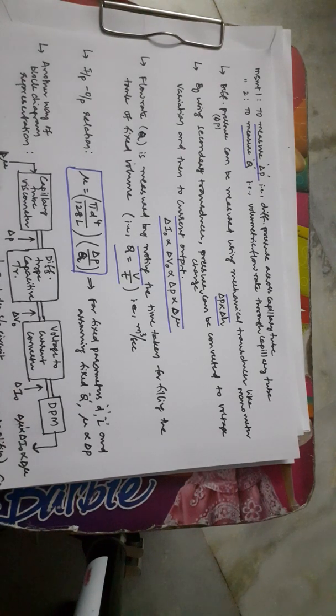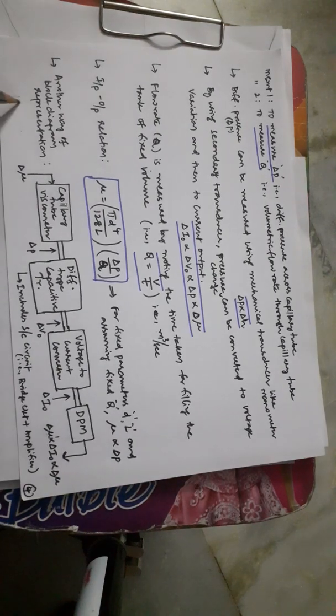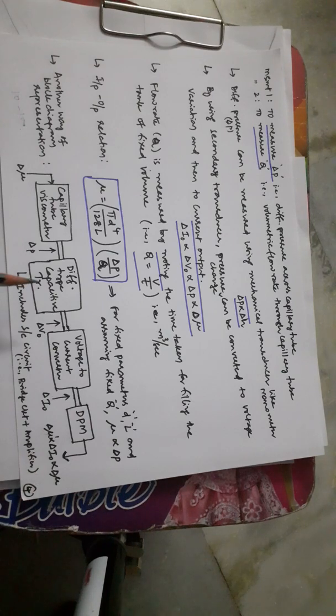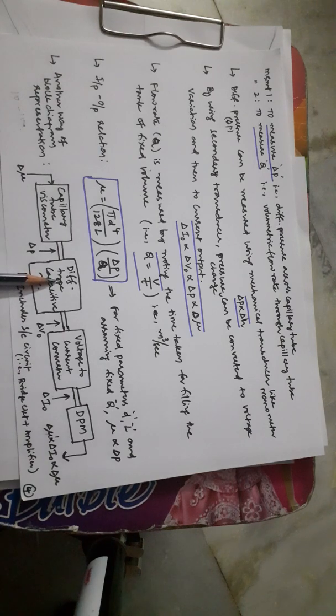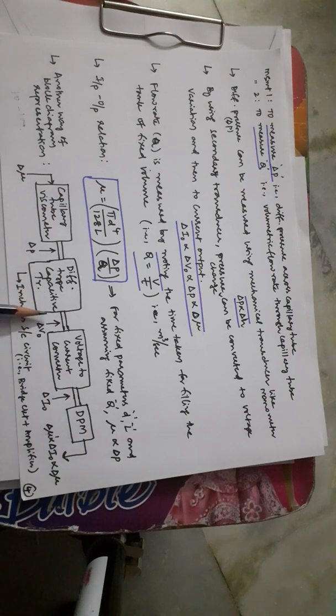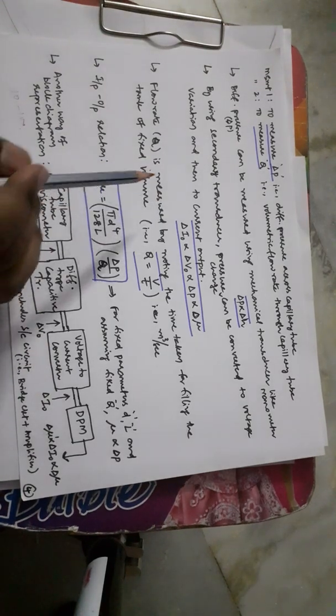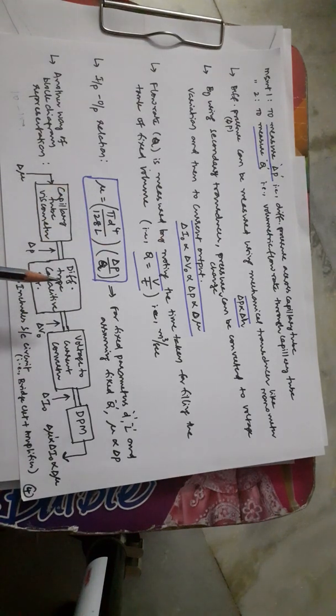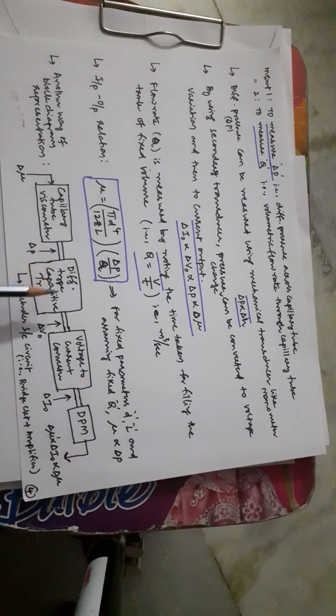If measuring a range of 10 to 100 centipoise, the output will be calibrated accordingly. One important point: the differential-type capacitor transducer comprises a diaphragm-based capacitor, a signal conditioning circuit — that is an AC bridge circuit — and an amplifier. The output voltage comes out after proper amplification. This concludes the working principle of the capillary tube viscometer. In the next video, we will see the variable area type viscometer.